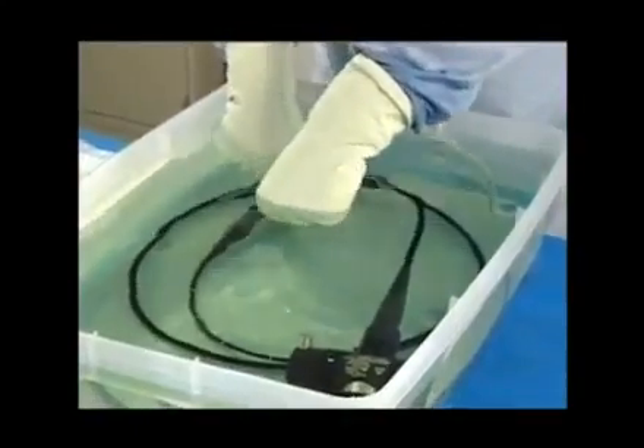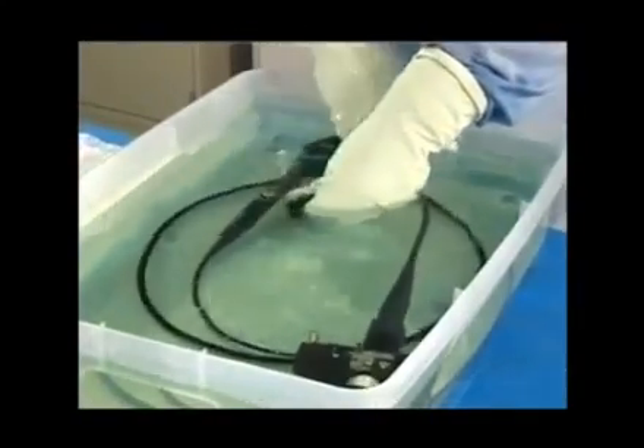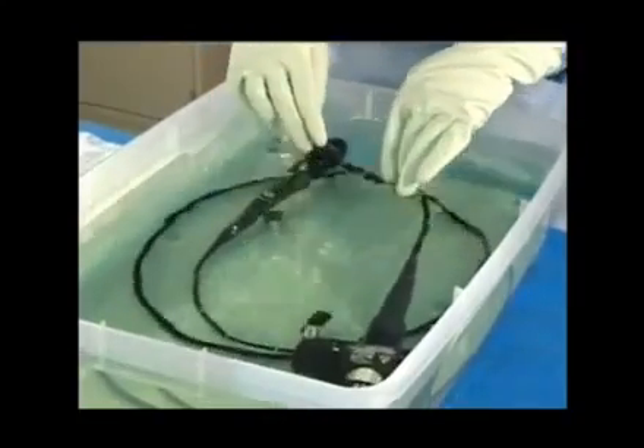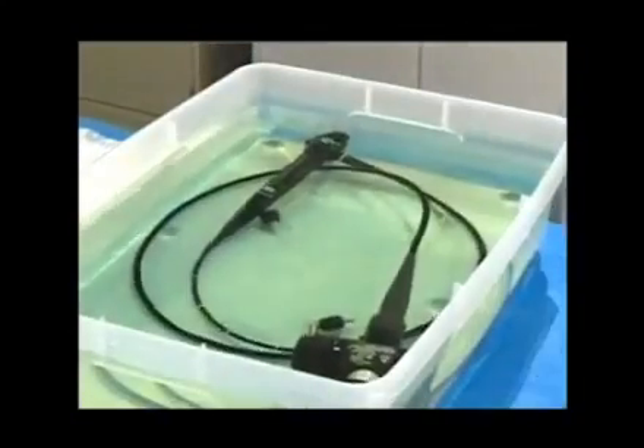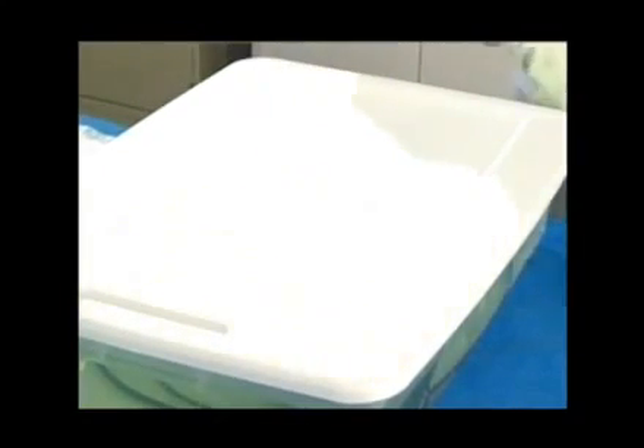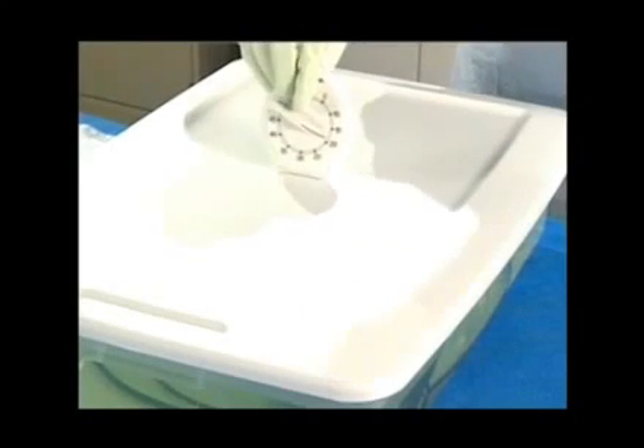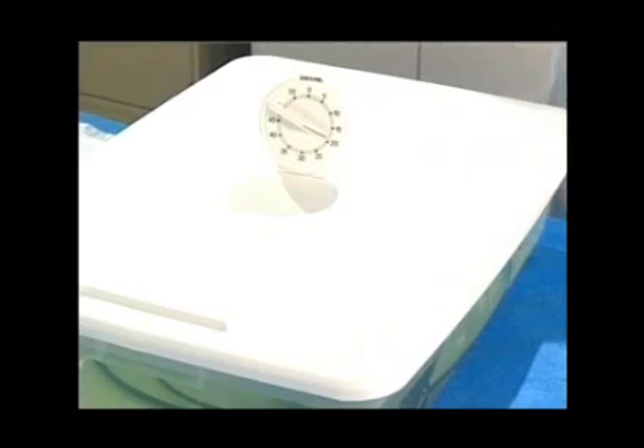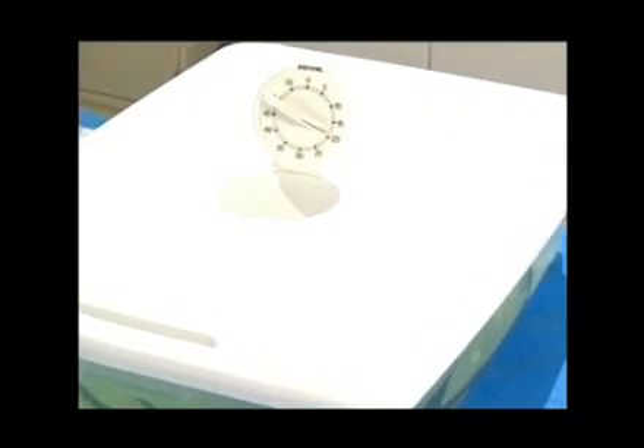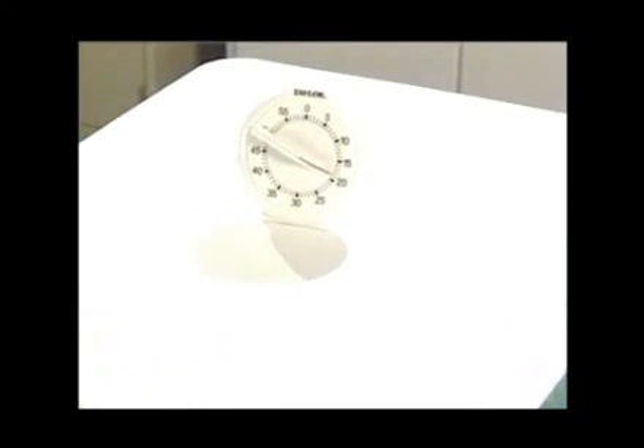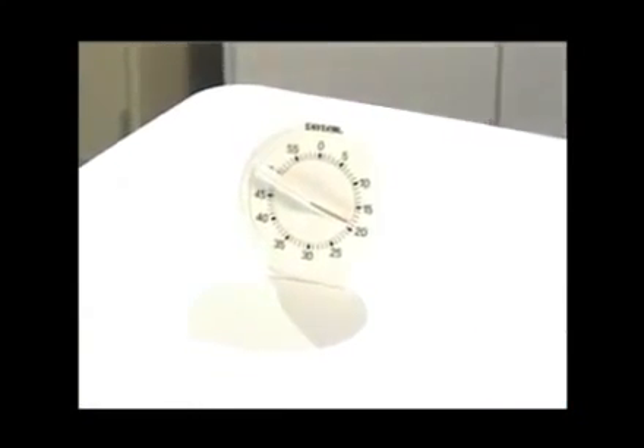Disconnect the syringe and the suction cleaning adapter from the bronchoscope. Place the adapter in disinfectant and make sure that all of the equipment is completely submerged in disinfectant. Cover the disinfectant basin with a tight-fitting lid in order to contain the disinfectant vapors. Disinfect the bronchoscope and cleaning adapter by soaking them in accordance with the disinfectant manufacturer's instructions. Use a timer to confirm that you are achieving the proper contact time. After soaking for the recommended period of time, reconnect the suction cleaning adapter.